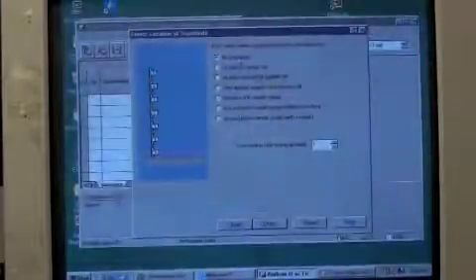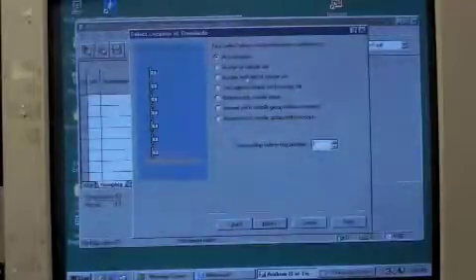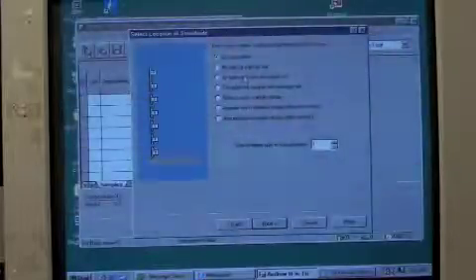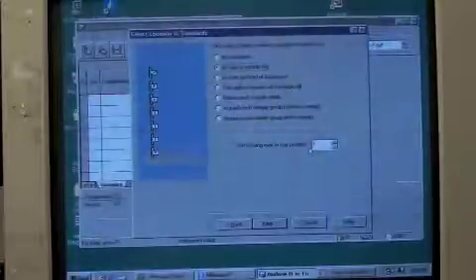We'll press Next. You can choose to run standards and samples, just samples, or just standards. In this case, we will run this sample setup with standards. We're going to choose to place standards at the start of the sample set. You indicate which vial position you're going to start from on the tray itself — we'll go with position number one. Next.